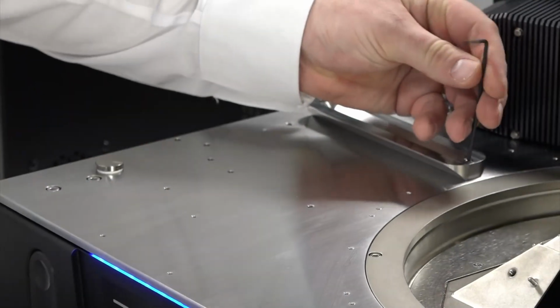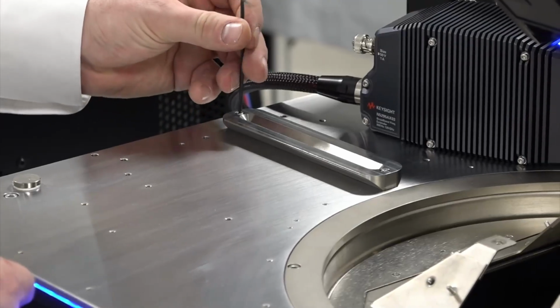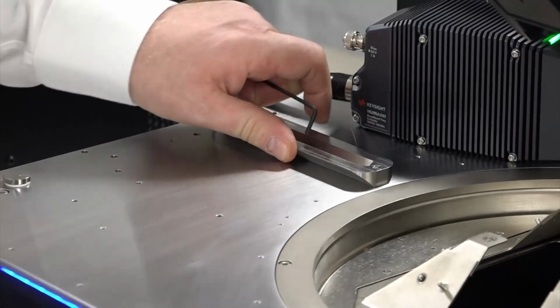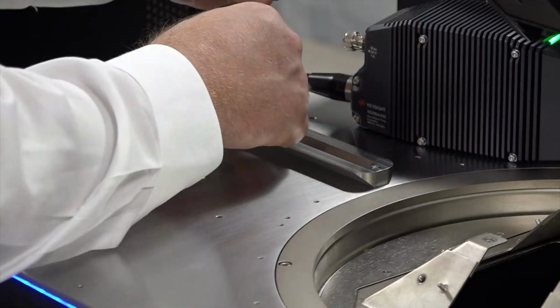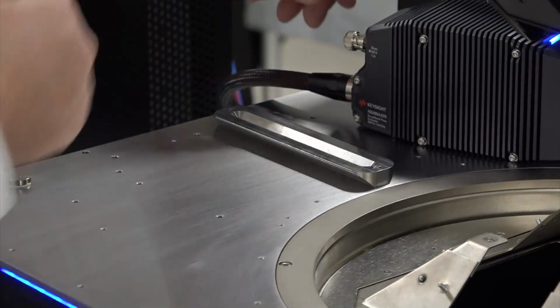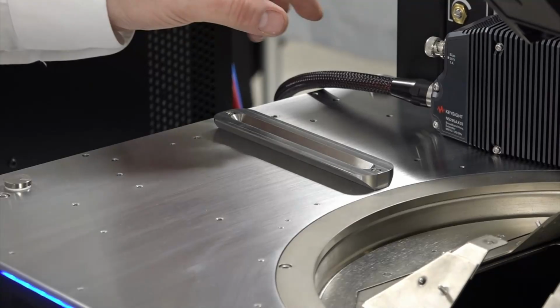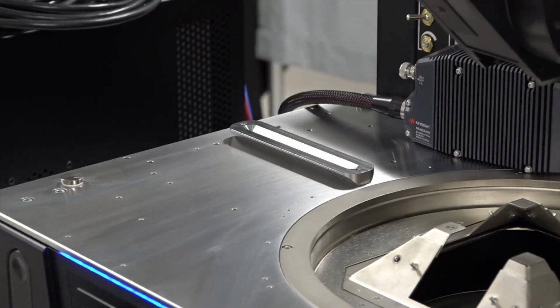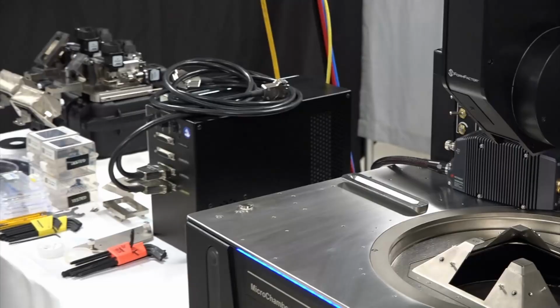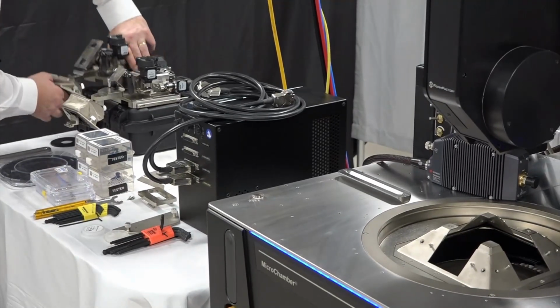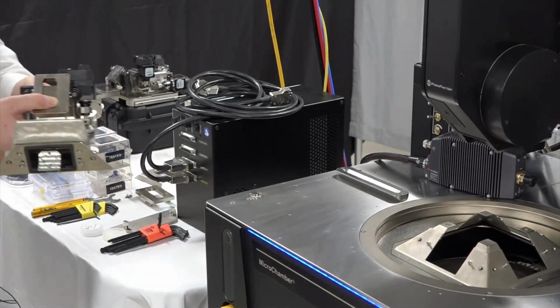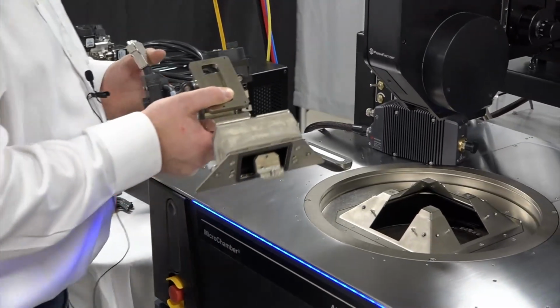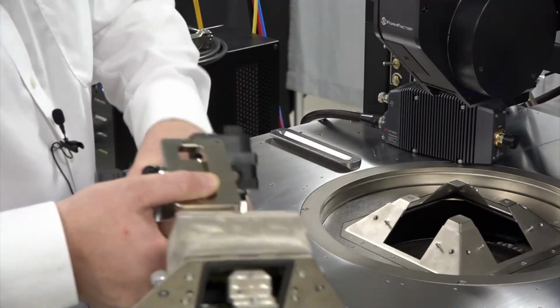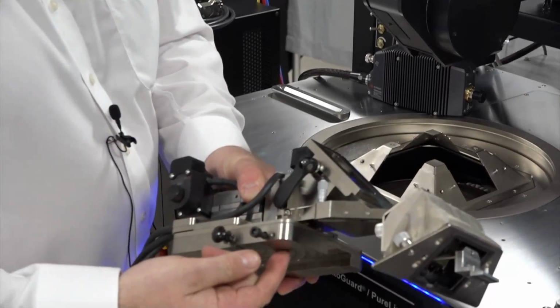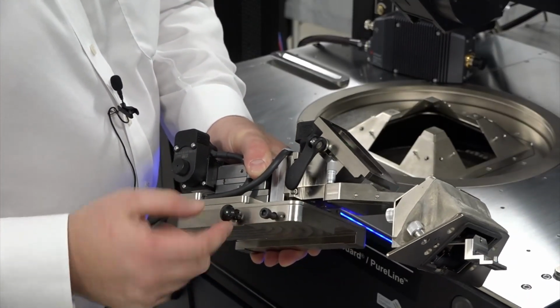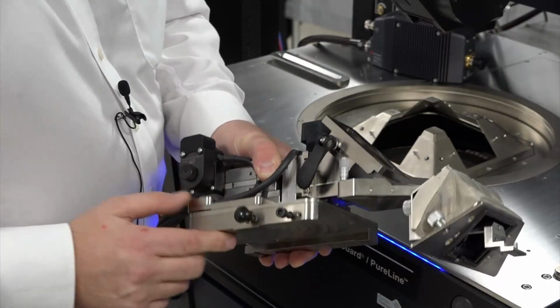Just going to tighten that up. Just give it a little wiggle, make sure it's pushed slightly biased to one side. And that's our rail in position. I'm going to drop my positioner straight over the top of it. In this case, before I mount the positioner, I make sure that the mounting screw is loose. If you have difficulty getting it on, this can be pulled back to give a little bit more clearance.